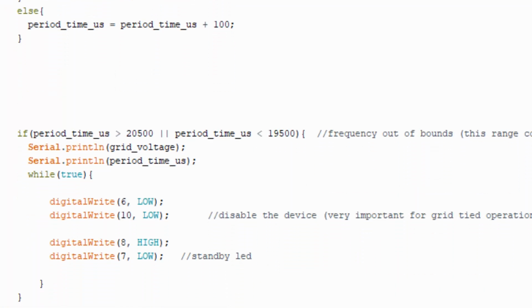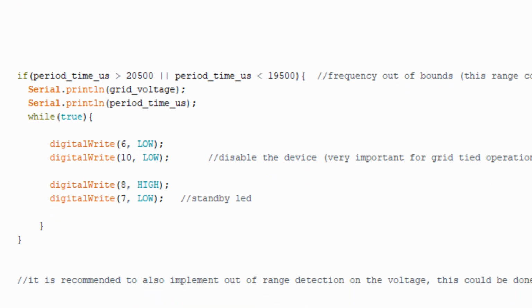So what we need to do in the code running on the Arduino is check if the period time, and therefore the frequency, is within a certain range. If it's outside of that range, the inverter will actually turn off and go into standby mode.